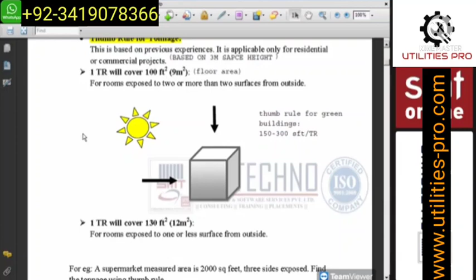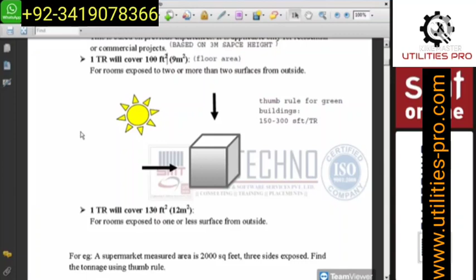And we'll do one simple example. The thumb rule is simple. If you know the floor area, divide the floor area by 100 if it is exposed and you'll get the tonnage, or divide by 130 if it is not exposed, and you'll get the tonnage, right? Simple. So here you see a simple example. A supermarket measures an area of 2000 square feet, 3 sides exposed. Find the tonnage using the thumb rule. 3 sides exposed means this rule is applicable, right? So 2000 divided by 100, 20 TR is required.